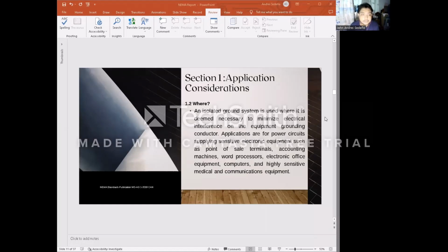Now, where should we consider this application? An isolated ground system is used where it is deemed necessary to minimize electrical interference on the equipment grounding conductor. Applications are for power circuits supplying sensitive electronic equipment such as point-of-sale terminals, accounting machines, word processors, electronic office equipment and computers, and highly sensitive medical and communication equipment.